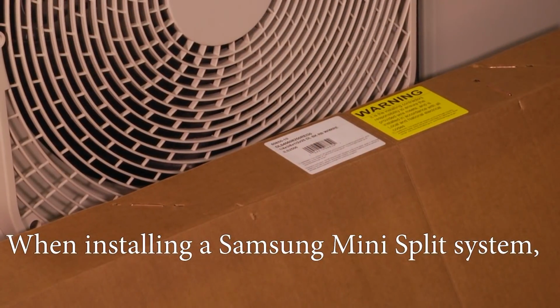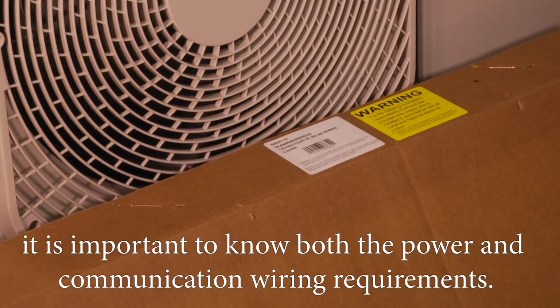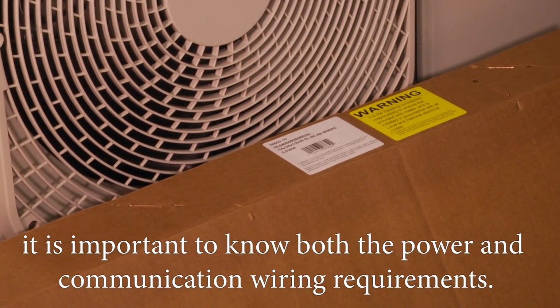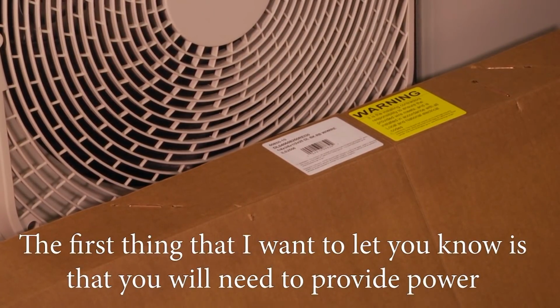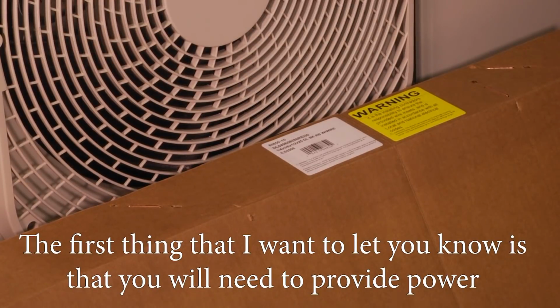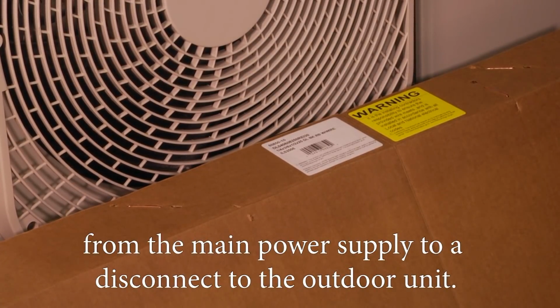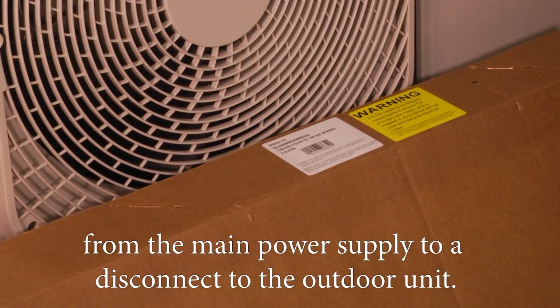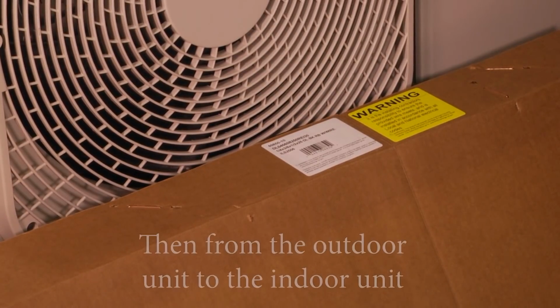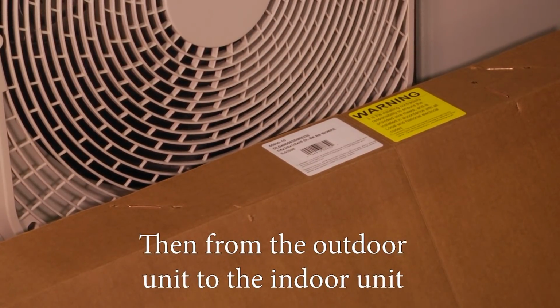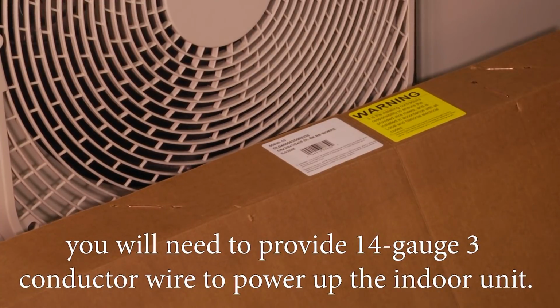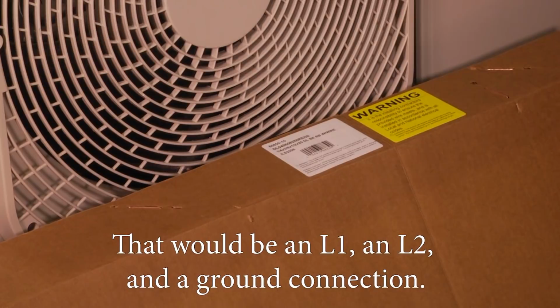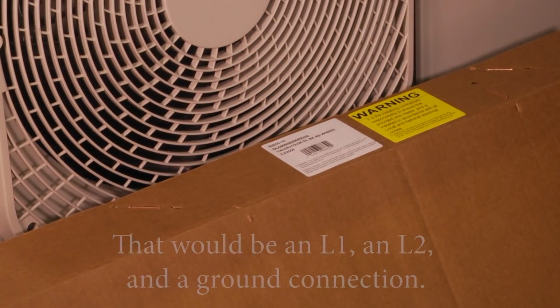When installing a Samsung mini split system, it's important to know both the power and communication wiring requirements. The first thing that I want to let you know is that you will need to provide power from the main power supply to a disconnect to the outdoor unit. Then from the outdoor unit to the indoor unit, you will need to provide 14 gauge 3-conductor wire to power up the indoor unit. That would be an L1 and L2 and a ground connection.